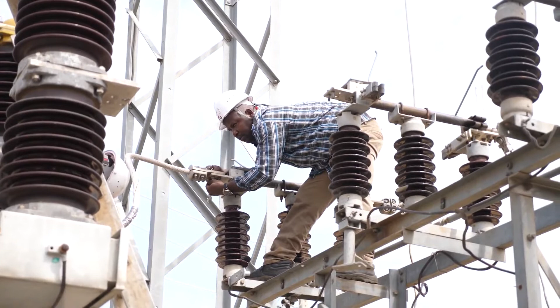TCN is also using its pool of veterans to develop more capacity in transmission grid management. This, according to a retired principal manager at the Karo Substation, is an innovative strategy that has helped to advance the company. He also described the capacity of the Karo Substation where he works at present. We have 2 by 60 MVA transformers, 132/33 kV transformers. Each is 60, so combined we have 120 MVA here.